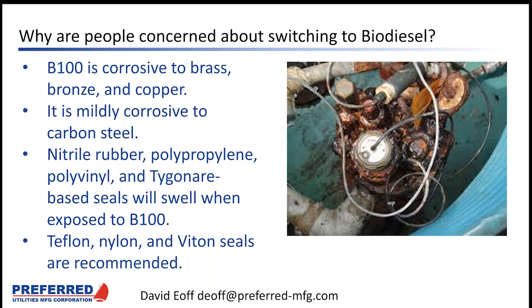The first issue of concern with biodiesel is it is corrosive to metals containing brass, bronze, and copper. It is much less corrosive to carbon steel, and stainless steel resists biodiesel corrosion almost completely. The other concern is swelling of rubber seals and O-rings. If you don't get rid of your rubber components, they will swell and potentially cause problems. This affects pump seals, valves, switches, and other instruments with seals exposed to the oil.